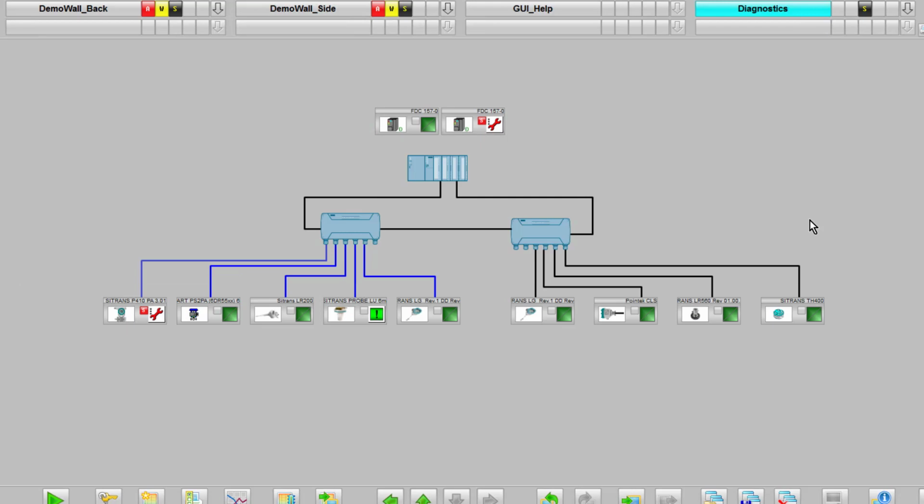So there you have it, the PDM maintenance station. As I said, it doesn't really matter what the PLC is, because maintenance station is not looking at the PLC, it's looking at the open protocol networks underneath, so Profinet or Profibus. And once you're onto those two physical protocols, then we can start bringing back the diagnostics from the smart instruments installed on those networks.